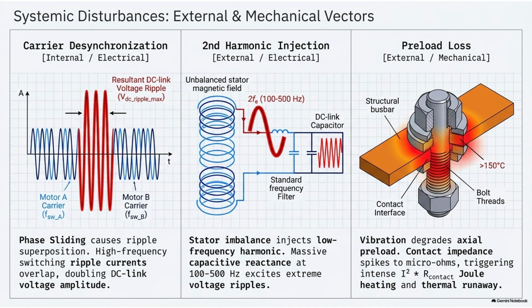It does. And because heat generated by electrical resistance is calculated by the square of the current. Wait, the square of the current? Yeah, so doubling that ripple current doesn't just double the heat. Oh, wow. It quadruples it. Right. A software timing glitch physically bakes the capacitor from the inside out in a matter of seconds. The thermal load just completely overwhelms the component's ability to dissipate heat, leading to rapid melting of the internal film.